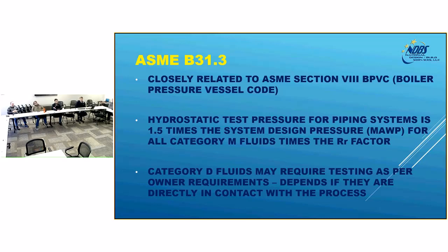So if you have a hot water system or a category M fluid system that's operating at high pressures or temperatures, you have to adjust the testing because the stress that pipe or vessel is going to undergo at the higher temperature is different than what it is at ambient temperatures. So we have to define those as the engineer on the job.